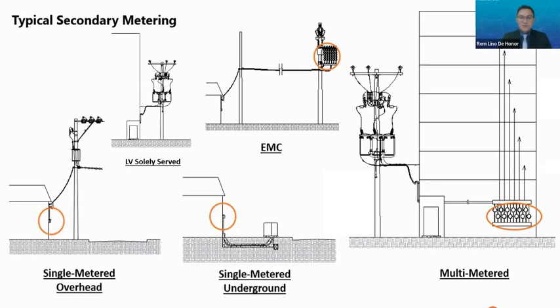Also, here are examples of secondary metering. First is the single meter overhead. The low voltage solely served, these are the solely served transformers for private buildings or industries, where the transformer is intended only for them. EMC, or Elevated Meter Center, is what we commonly see, where the meters are elevated. Single metered underground is for high-end subdivisions. And multi-metered is for condos and high-rise buildings.